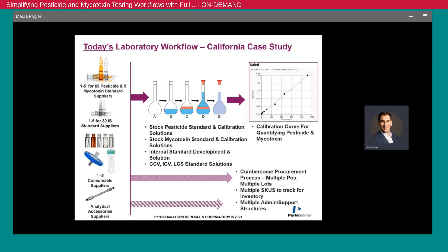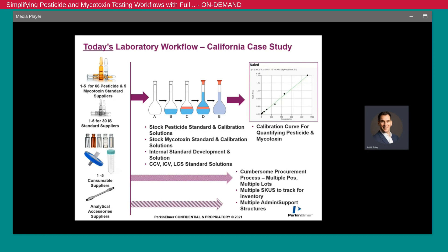Let's take a look at California as a case study to understand where some of this experimental error can come from. If we look at the pesticide and mycotoxin testing requirements, labs need to source 66 pesticides and five mycotoxin standards, which often come from a handful of suppliers. They also need to work with suppliers for internal standards and consumables. This is a very cumbersome process and leads to quite a lot of inefficiencies. When it comes to preparing the calibration standards and quality control standards, we also see a very laborious process on the bench, with stock solutions being mixed and then subsequent dilutions for each calibration curve point — this can contribute error systematically if not performed correctly.